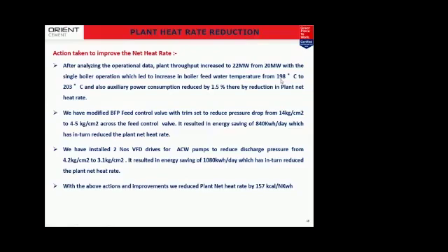So in that case, just to improve the efficiency of the boiler and the feed water temperature, we have gone up by 2 megawatt. Earlier, we were producing only 20 megawatt with a single boiler operation, but now we are generating 2 megawatt excess. It means we have overloaded the boiler to 98 TPH, of course within the limits of the overloading. We have improved our power generation to 22 megawatt, which in turn has raised our feed water temperature from 198 to 203 degrees centigrade. This subsequently reduced our power consumption by 1.5%. As you all know, since we have reduced the auxiliary power consumption, it has reduced the plant net heat rate also.